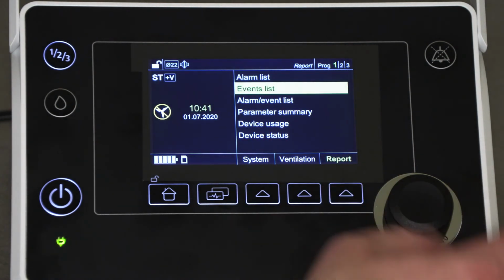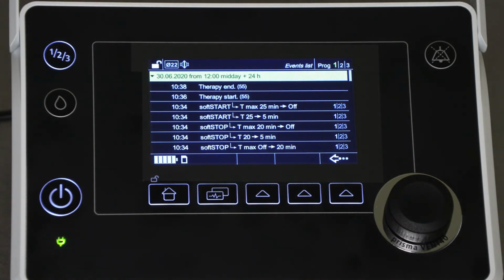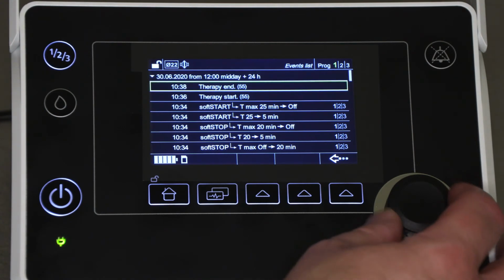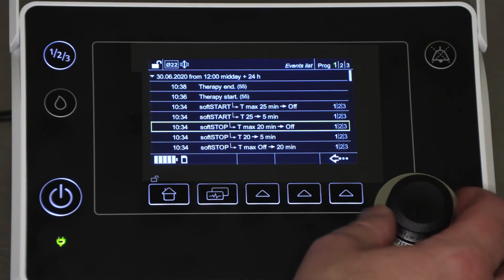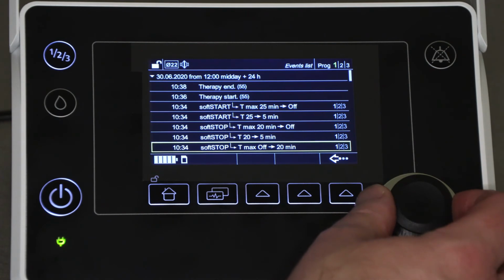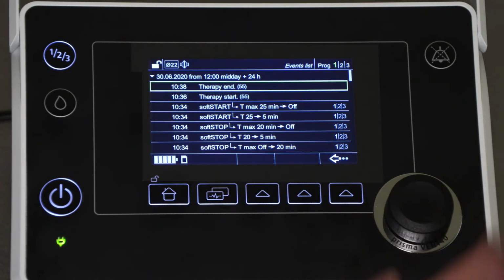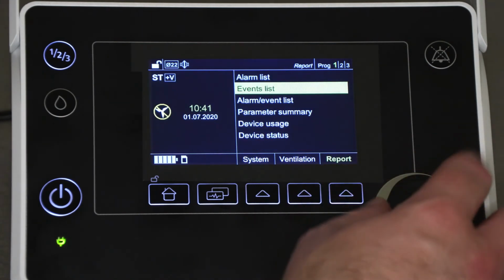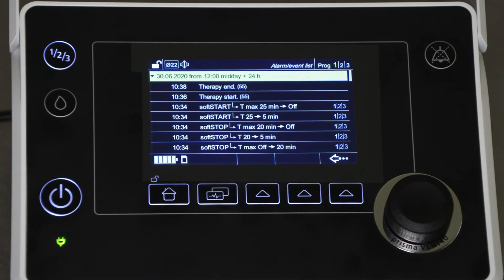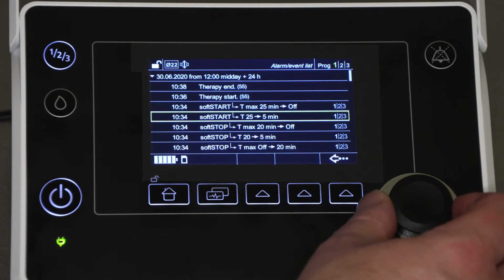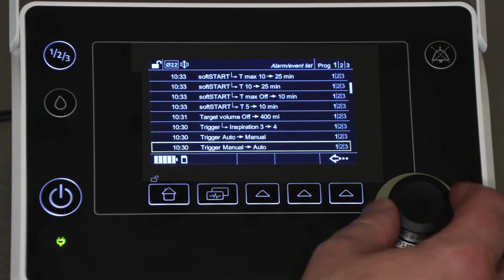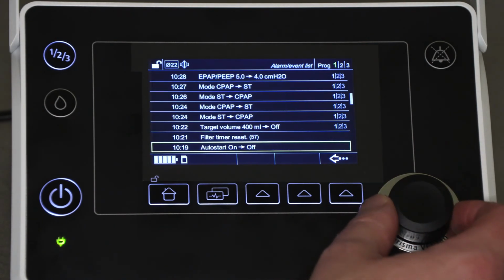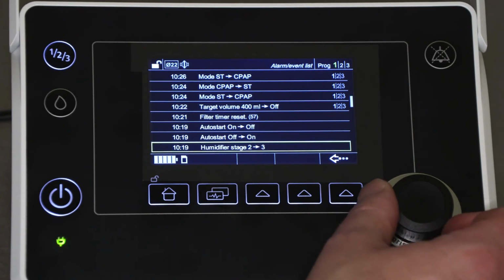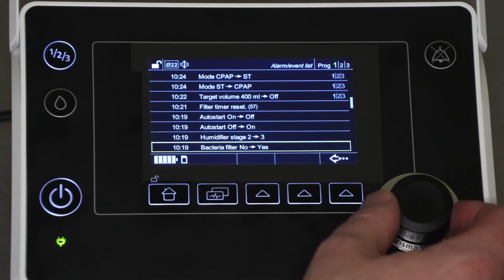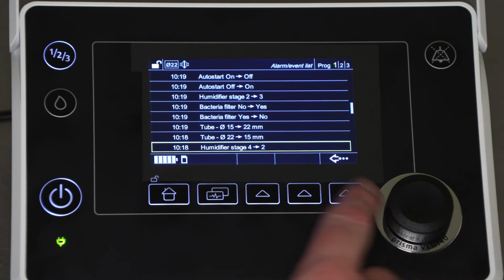Next, there's an event menu, which shows a list of all occurrences of therapy start and stop, and also shows information about what settings were changed and when. The alarm event list is simply a mixture of both of the previous information lists. Because they're together, it's easy to get a timeline of events, for example, if and when an alarm occurred, and if any buttons were pressed or settings adjusted before or after that alarm.